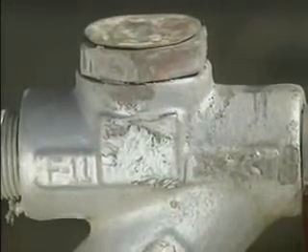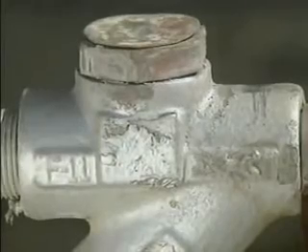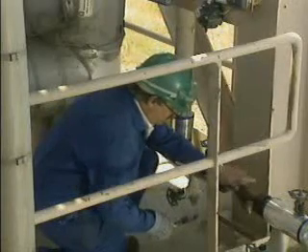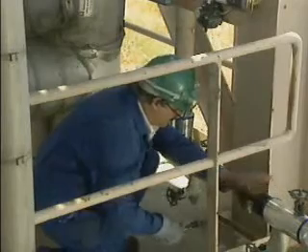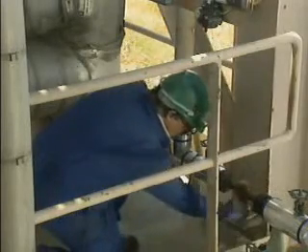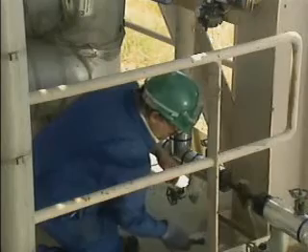Many of the maintenance problems associated with thermodynamic steam traps are due to wear of the trap components. Thermodynamic traps are very sensitive to scale or dirt that gets lodged on the seating surfaces. For this reason, a strainer should always be installed at the trap inlet. The strainer should be cleaned or blown down frequently to be sure that it remains free of debris and does not become clogged.